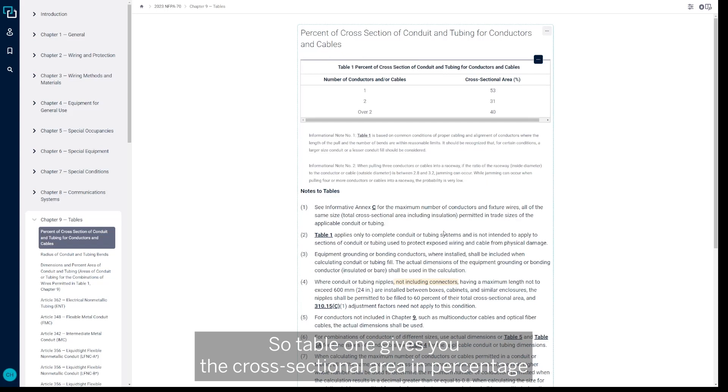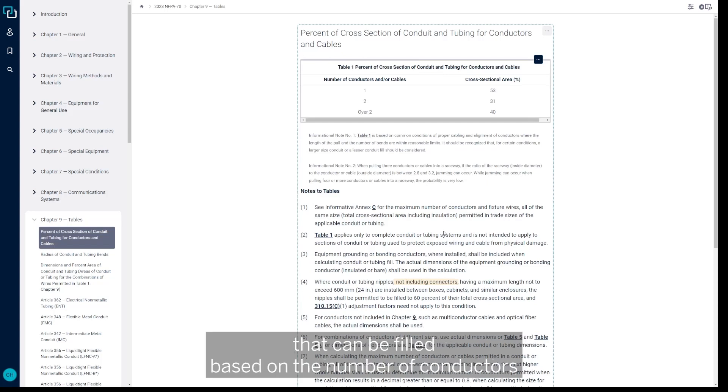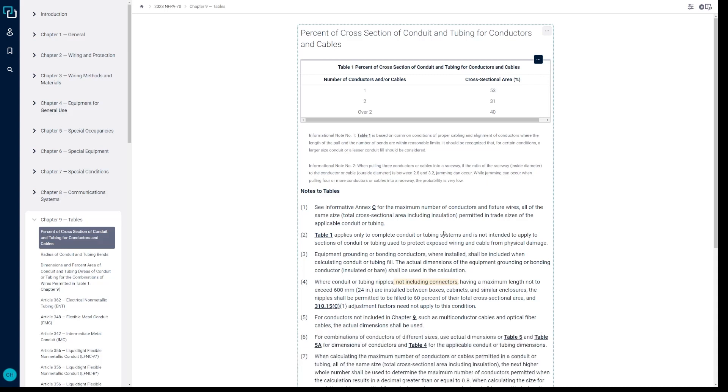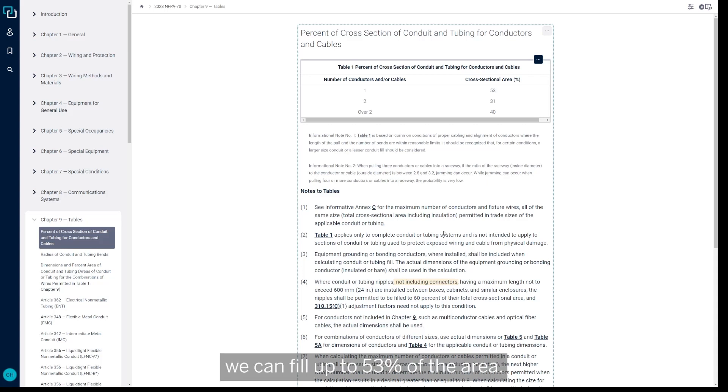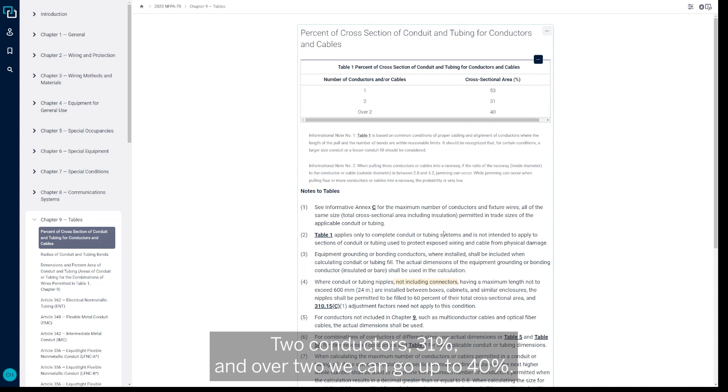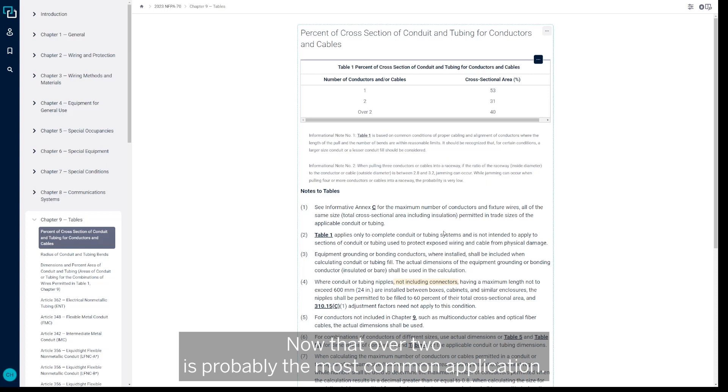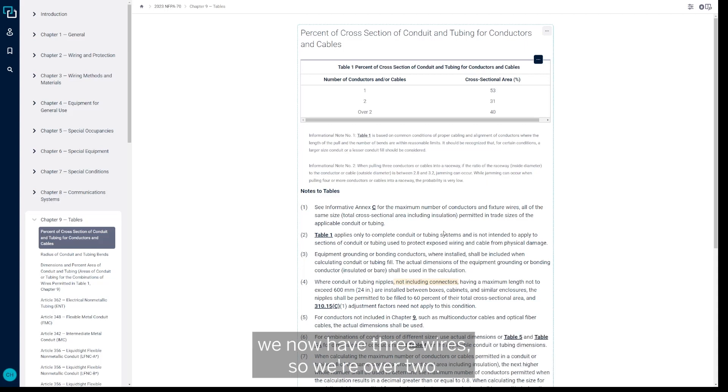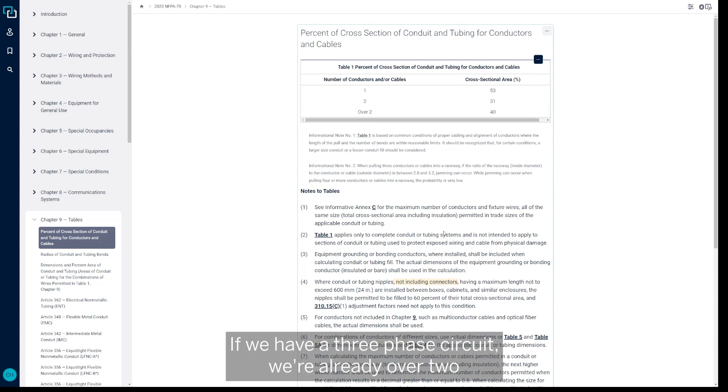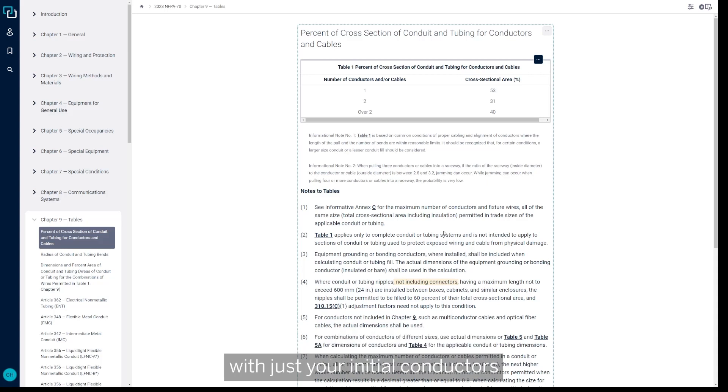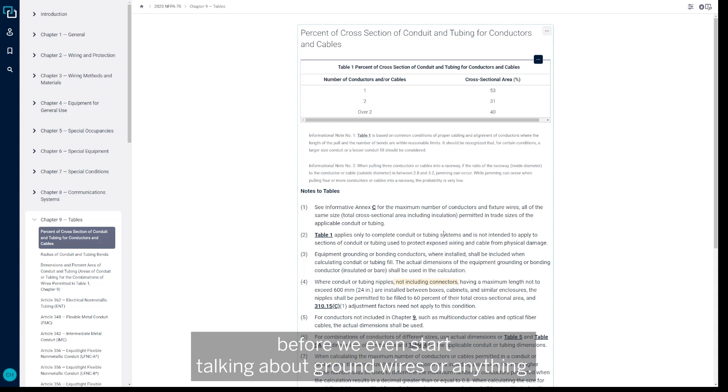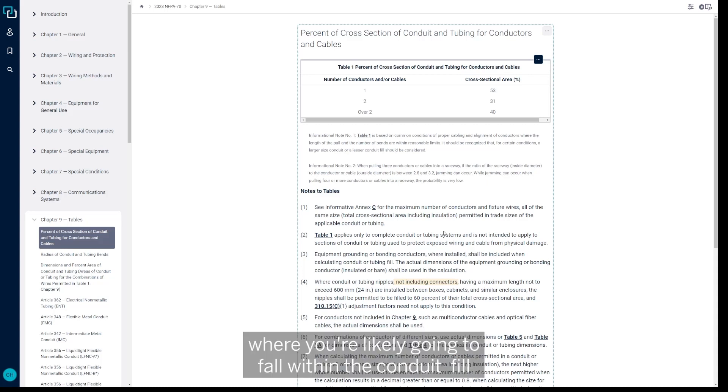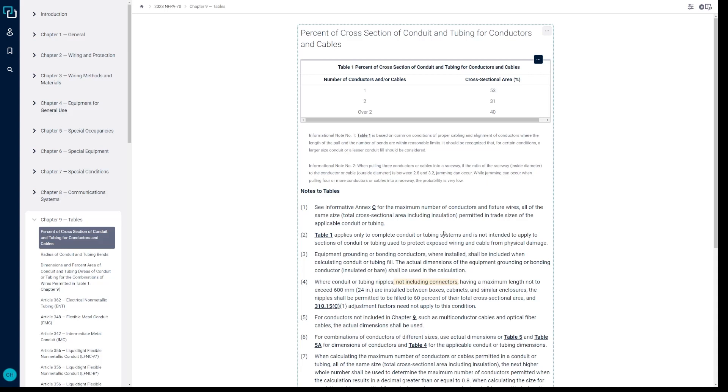And I want to look at Table 1 first just to kind of give you a breakdown of what we're going to see moving forward. So Table 1 gives you the cross-sectional area in percentage that can be filled based on the number of conductors or cables that are being pulled within that conduit. So if we have one conductor, we can fill up to 53 percent of the area. Two conductors, 31 percent, and over two we can go up to 40 percent. Now that over two is probably the most common application—even if we have a single phase circuit that we're pulling an equipment ground with, we now have three wires so we're over two. If we have a three phase circuit, we're already over two with just your initial conductors before we even start talking about ground wires or anything. So that 40 percent is going to be the typical area where you're likely going to fall within the conduit fill calculations that you're doing.